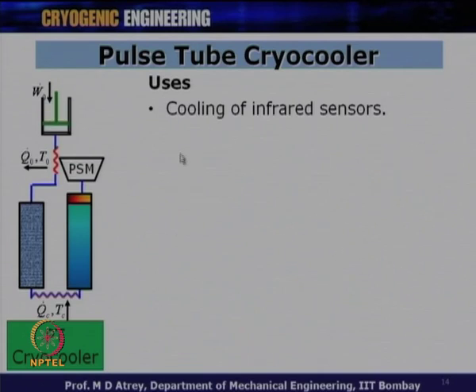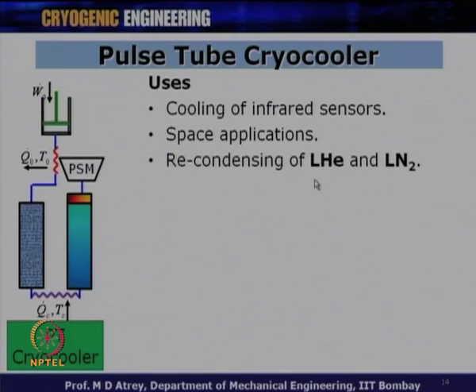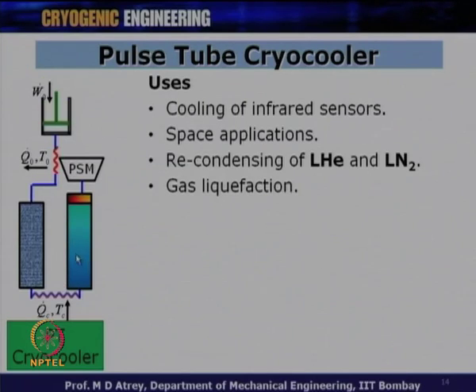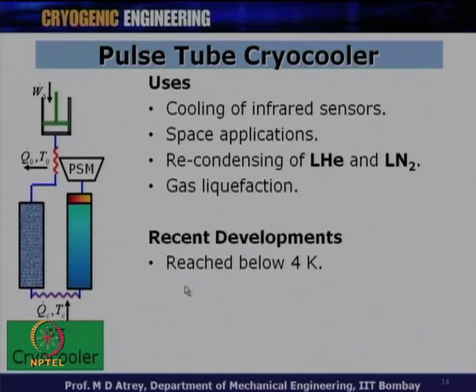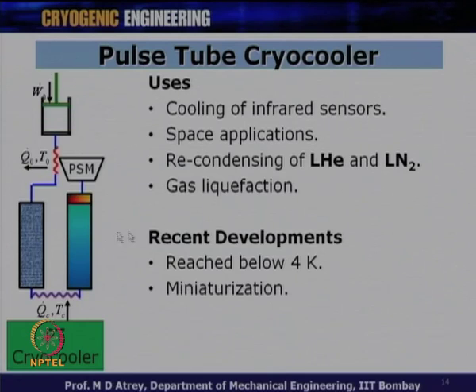Uses of pulse tube coolers include: cooling infrared sensors for space applications; recondensing liquid helium and liquid nitrogen; and nitrogen or helium liquefaction depending on whether single-stage or two-stage. Recent development allows less than 4 K temperature using a two-stage pulse tube cryocooler, and miniaturization is possible with a Stirling-type pulse tube cryocooler. Hence, pulse tube coolers are very important candidates among cryocoolers.